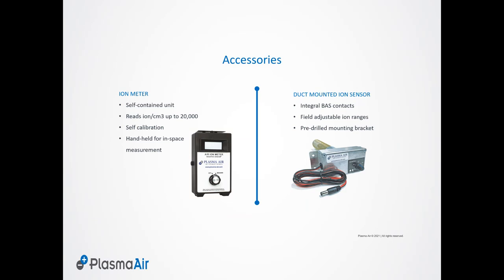Another option we have is to install a duct-mounted ion sensor. This acts like a thermostat. You dial in the number of ions you want, and if it falls below that level for any number of reasons, it'll send a signal back to the building automation system that we're below the ions. If you do not get a signal, that means the ions are being produced at the level you want them produced. So those are a couple ways we're verifying that you're getting the ion density you need for air purification.